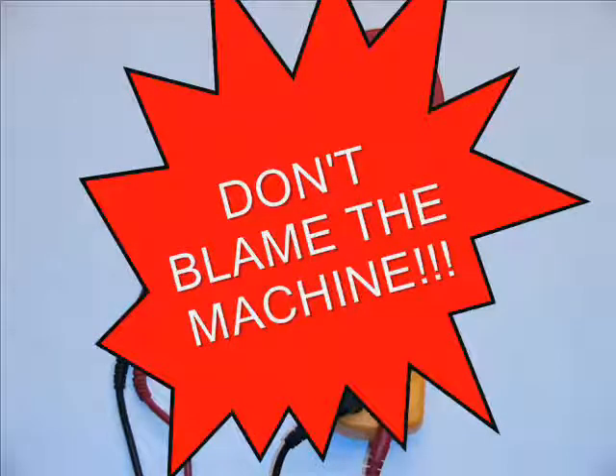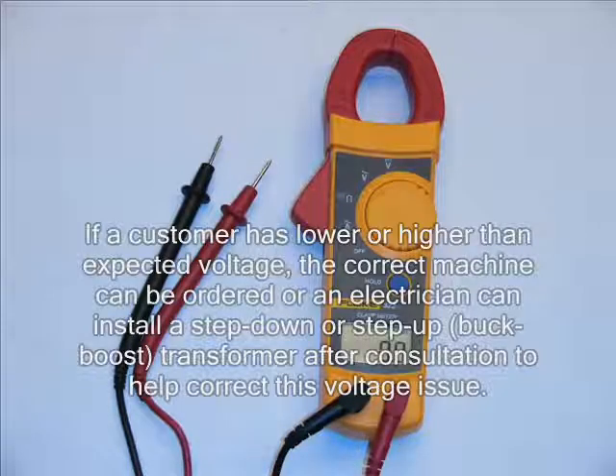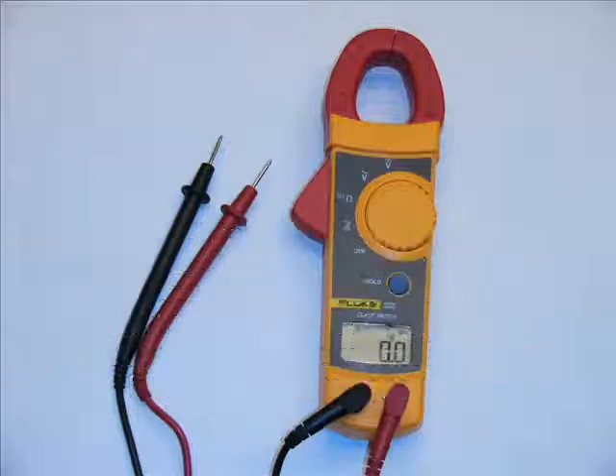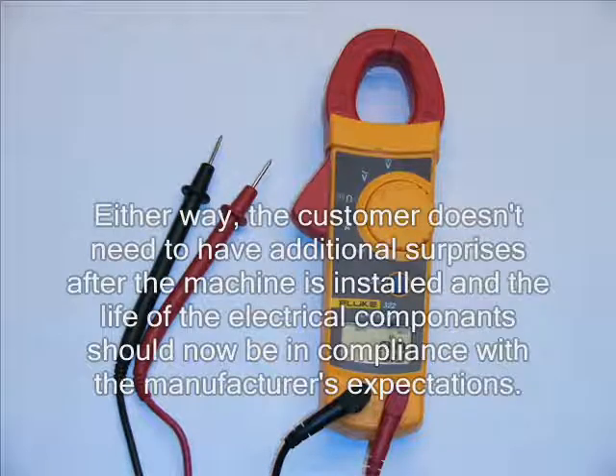Don't blame the machine. If a customer has lower or higher than expected voltage, the correct machine can be ordered, or an electrician can install a step-down or step-up buck-boost transformer after consultation to help correct this voltage issue. Either way, the customer doesn't need to have additional surprises after the machine is installed, and the life of the electrical components should now be in compliance with the manufacturer's expectations.